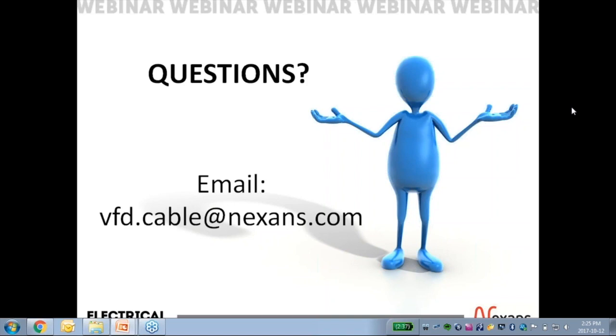The Canadian market cable is rated 1 kV, designed for 600 volt rated systems. Now, with a 1 kV rated insulation system on our VFD cable, it could easily withstand voltage spikes in excess of 2000 volts. Keep in mind, a typical VFD operating at 600 volts would see voltage spikes upwards of 3.1 times, or approximately 1900 volts. So no issue there. In the US market space, we offer a 600 volt rated cable, again with cross-linked polyethylene insulated conductors and the aluminum sheath armor, and it's capable of operating with 480 volt drives, no issue.